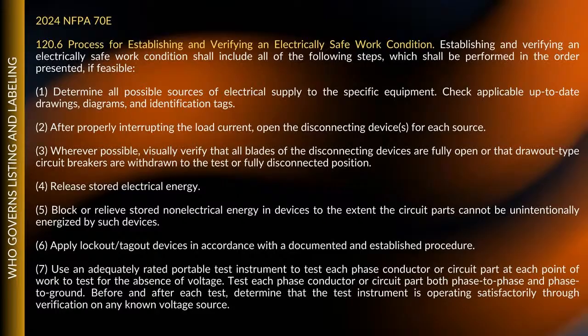So just so everyone knows what this is talking about - I've had to deal with this before when dealing with 13.8 and 4160, a lot of these transmission lines are coming off the gate. So just because you throw that switch and visually verify the disconnect blades are open, you think, all right, cool, everything's good. But you still have about a mile or half a mile of conductor that has an induced voltage. So you have to go and release that stored energy. A lot of people think, oh man, I shut it off, I'm good to go. It's like, no, there's still 13,800 volts of stored energy in that conductor that you have to release.